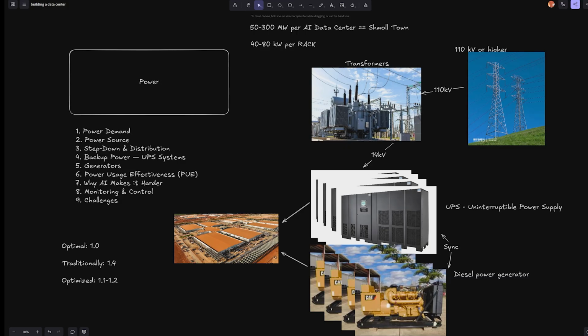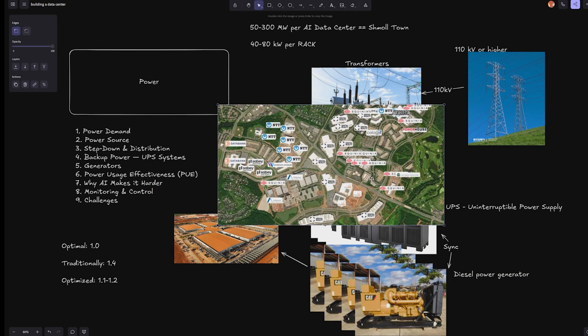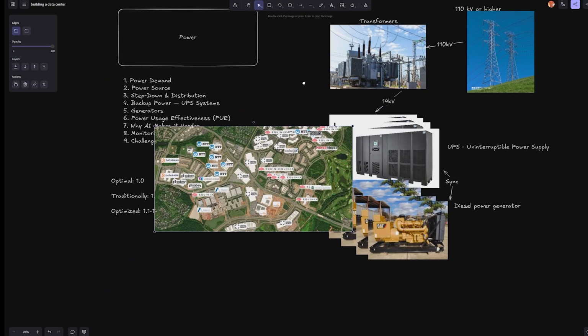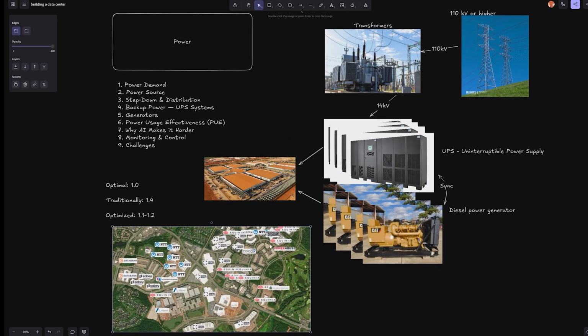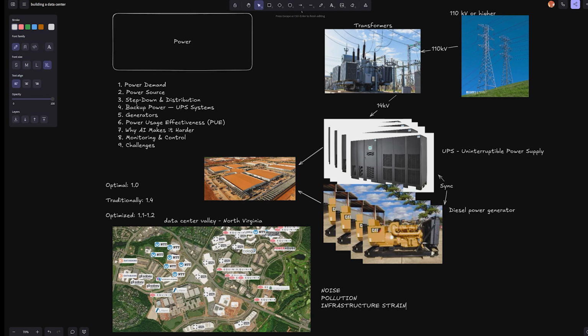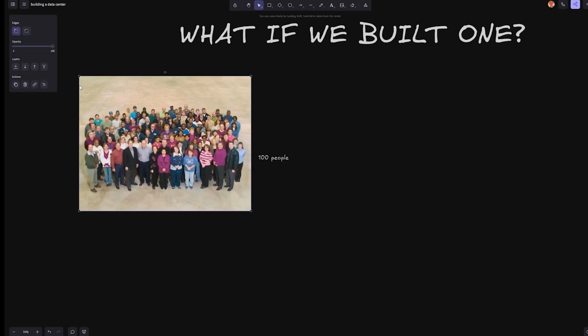One of the big ones is the grid connection delay. This requires multiple years of approval due to the amount of strain that it puts on the system. Also, there is local opposition due to noise, emissions, and grid strain. If you want more details on this, by the way, have a look at Data Center Valley in North Virginia. There are multiple interviews with the locals that report an absurd amount of noise, often leading people to sleepless nights and, frankly, just insanity. In short, power is the lifeblood of an AI data center. Electricity flows from high voltage lines through layers of transformers, batteries, generators, everything feeding thousands of GPUs that never sleep. One flicker and the entire artificial brain forgets what it was thinking. And then goodbye, millions.